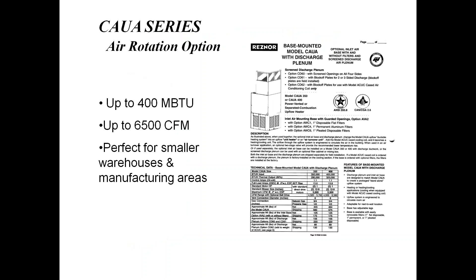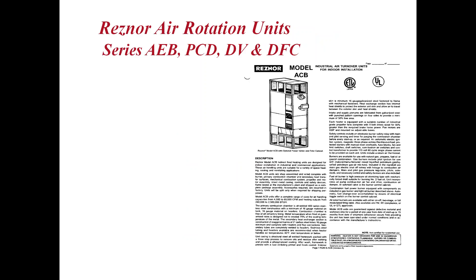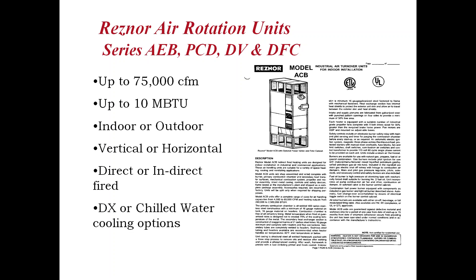If you're a small warehouse, converting a warehouse into a shop area, or have a fire hall or church building where you have heating now but need cooling without going through extensive ductwork, this is a good application. The larger air rotation units — AEBs, PCDs, DVs, and DFCs — are higher capacity, up to 75,000 CFM for large warehouses and up to 10 million BTUs. These units can be mounted indoors or outdoors, vertical or horizontal, with direct or indirect fired options available. We do not offer a cooling coil on direct-fired equipment, but DX or chilled water cooling is an option. We can help with layout and design for this product.